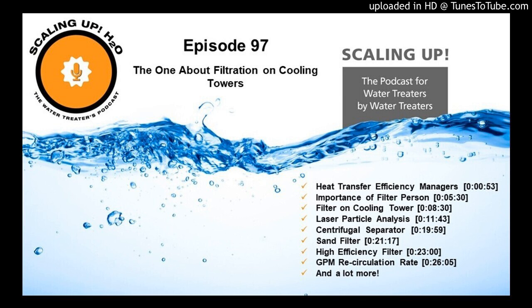It's a seasonal thing. Large clients that have the money to have particle analyses done periodically, like once a quarter, see it's really a seasonal thing. Everything changes every season in any significant system, whether because of the pollen count or the temperatures outside. The winter cold weather is generally going to have less particulate and fewer problems with the water. The load on the system is usually lower in the winter, so the total volume of air going through a system to be washed out is smaller. In the spring, a lot of times people open up all kinds of systems that were closed all winter, and when that happens, there's frequently a lot of material coming in. So to me, there are always ups and downs, jumping way up on particles and way down on particles.